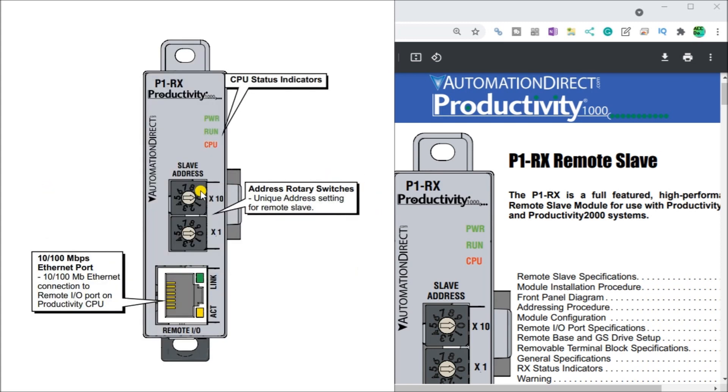Rotary dials will set your unique address for your remote slave unit. And this must be set from anywhere from 1 to 99. And 00 is the default, which comes out of the box. So this must be set prior to powering up the unit or you will get an error.